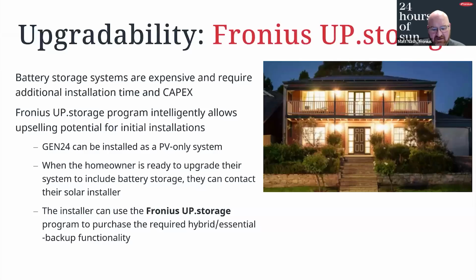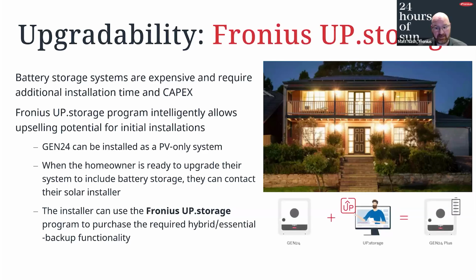As I stated before, the Gen24 is an upgradable hybrid inverter. So as everybody's aware, battery storage is pretty expensive. And it does require a lot of additional installation time and CapEx. So the Up.storage program allows you to have an upgrade path for your customers. So it can be installed as a grid tie only. And then when the system owner is ready to upgrade, they can do so through our web shop. And at that point, if it is on our SolarWeb monitoring portal, as soon as it's paid for, it'll actually download the file so you can go ahead and activate the battery backup functionality. So it essentially turns a Gen24 into a Plus model.